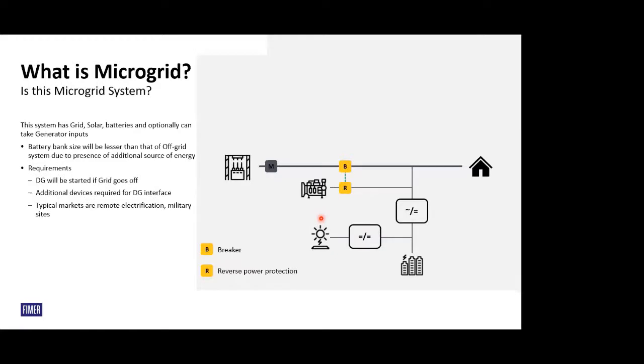Then we have one more system which can be grid integrated as well, sometimes with a diesel generator, and it also has a lot of breakers, relays and contactors to provide reverse protection for the generators. So it is often confused for a microgrid. This is a hybrid system where all the sources are connected in parallel without control on most of the sources like grid and generator. It tries to push as much power as possible as it sees the loads, and the impurities and bad qualities of the power, if you're using, let's say, biomass, are also passed on to the grid.